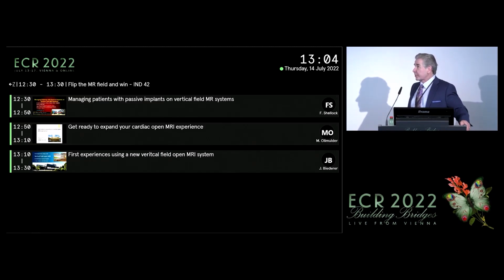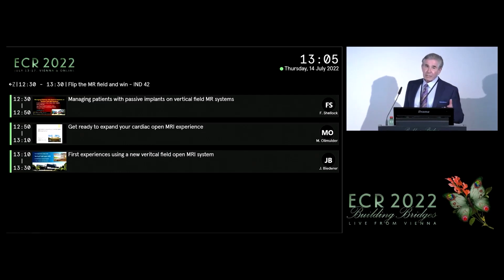Well, so the spatial gradient magnetic field, there is some torque at the very beginning, but it's not substantial, and those counter forces will overwhelm just about anything. And the fact of the matter is, very few medical implants are made out of material that's magnetic to the extent where it's going to pose a hazard. And I'm talking about things like 304 stainless steel and that type of thing.